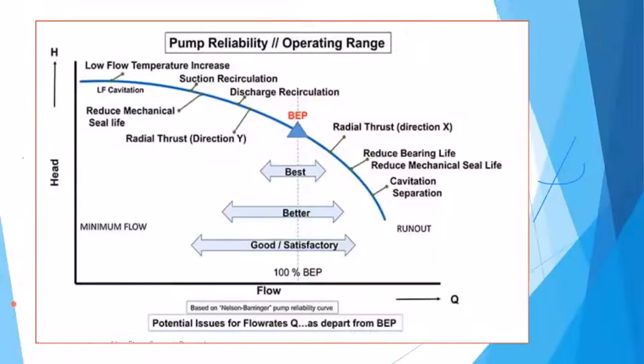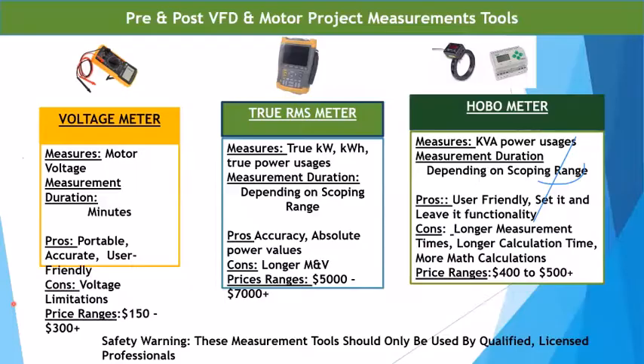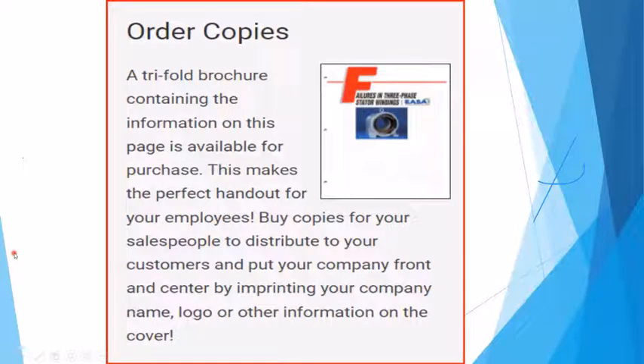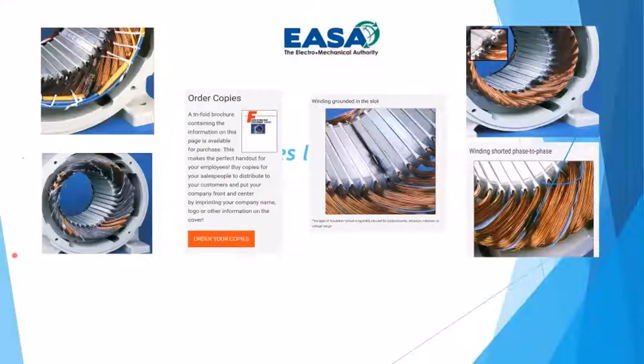So again, we go back to the metering, the input, the true RMS power being able to be read. Then they also have what they call HOBO meters, which basically record currents over time. There's also a trifold flyer available called "A Motor Tells a Story." If a motor fails, you can typically tell what happened. Inside this flyer, it shows you the situations that happen.